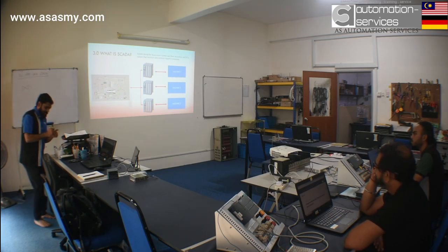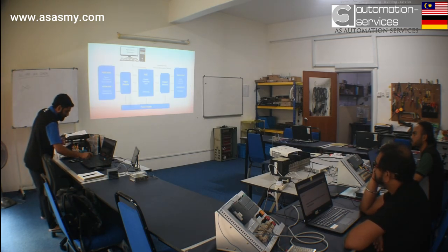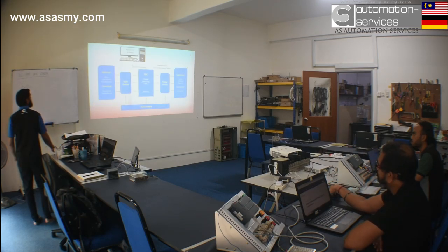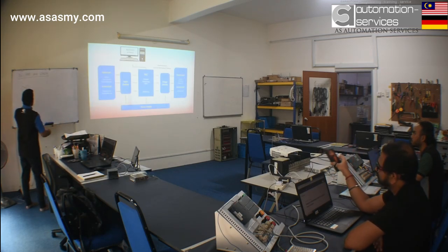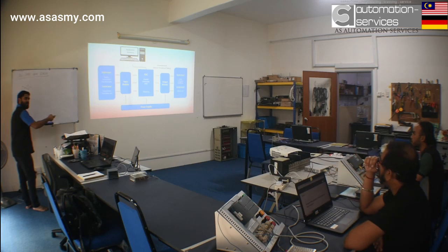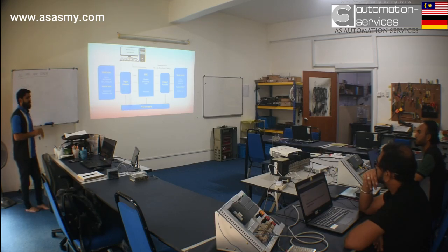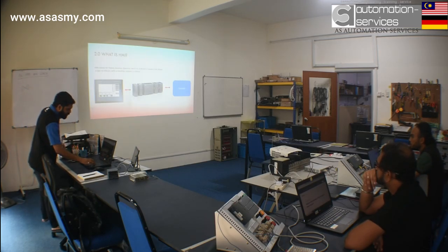So on could be green and off could be red. Then you have to put the address - like we saw with the output. So your valve will be your output, and you put the output address here. So when the PLC output is on, this will change color. That's how it works - in SCADA it's similar to HMI.